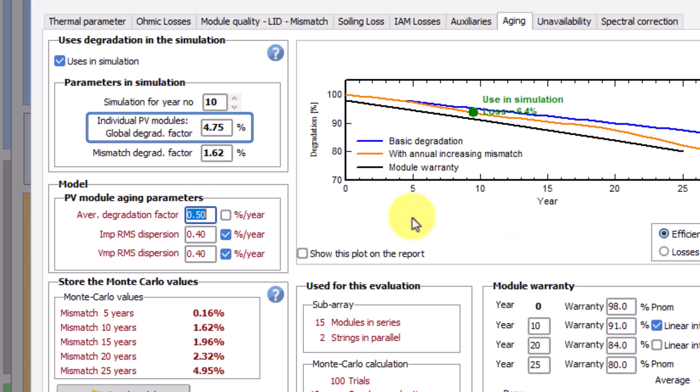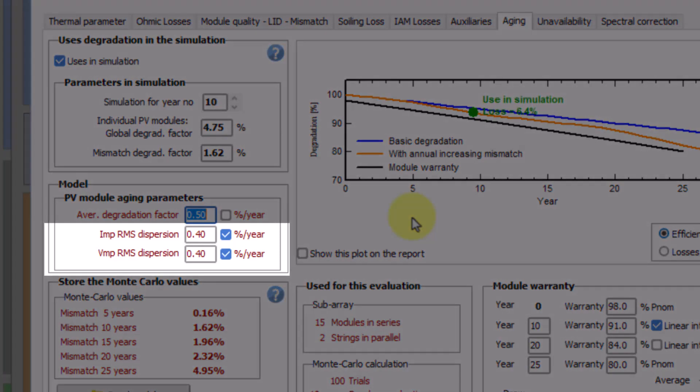Next, you can define the IMP and the VMP RMS dispersions. These parameters represent the variance of the MPP current and voltage. A low RMS dispersion rate means that the variance does not change significantly over time, meaning that the PV modules all age in the same way.